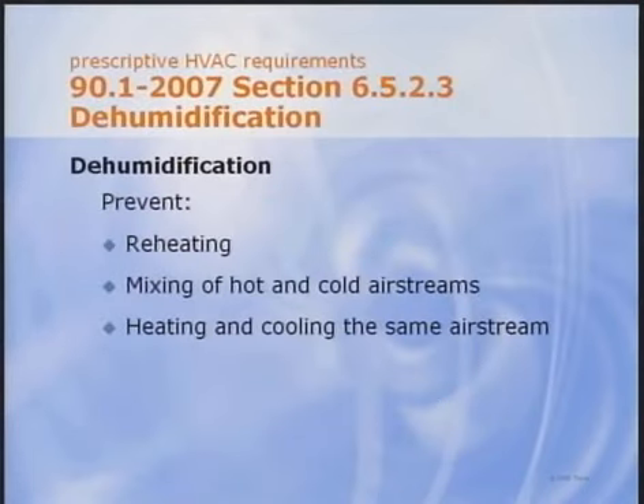Where humidistatic controls are installed, Section 6.5.2.3 requires controls to prevent simultaneous heating and cooling of the same airstream. But there are 6 exceptions. Exception A allows variable air volume, dedicated outdoor air, or 2-speed fan systems to use reheat if the airflow being reheated is first reduced to either 50% of the supply airflow or the minimum ventilation rate required by 62.1.